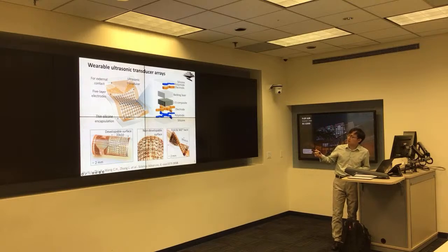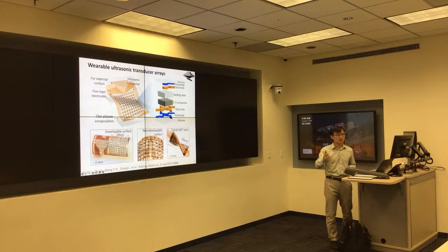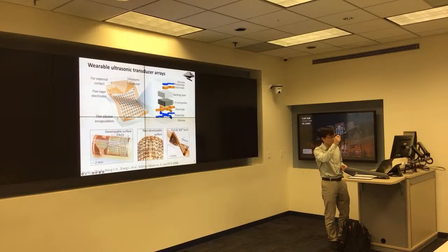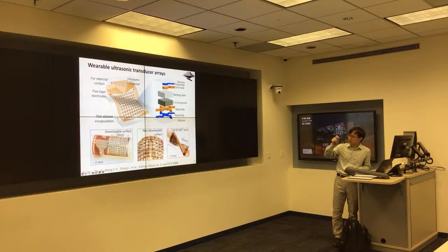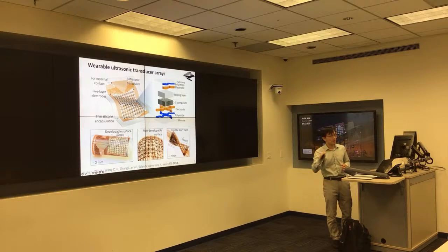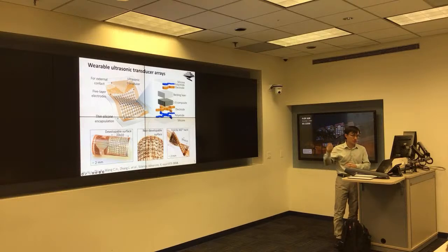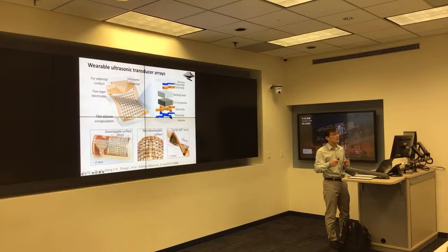And one unique structure of this piezoelectric transducer we used is a so-called 1-3 composite. It's basically those piezoelectric single crystal material embedded in a 2-dimensional polymer matrix, so that the vibration along the longitudinal direction is enhanced and the lateral shear vibration is suppressed, so we get more ultrasound transmitted into the human body. And at the bottom here, those images show how soft this device is. It's flexible, stretchable, and it can be twisted, showcasing the mechanical compliance of this device.